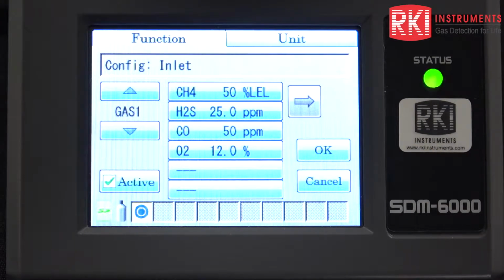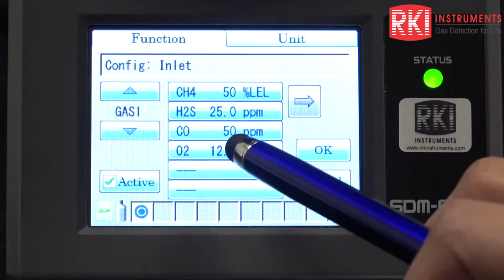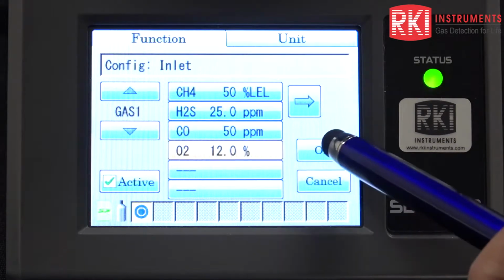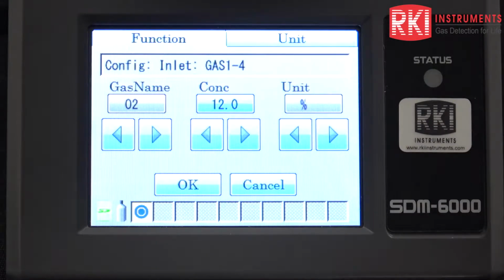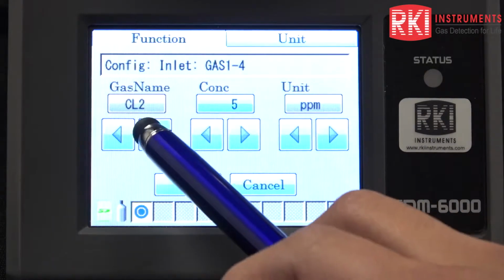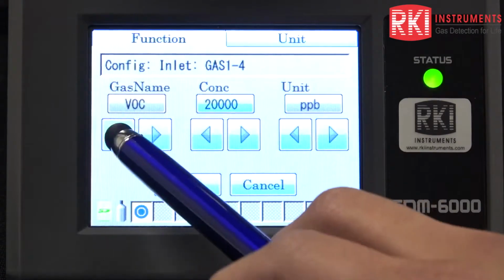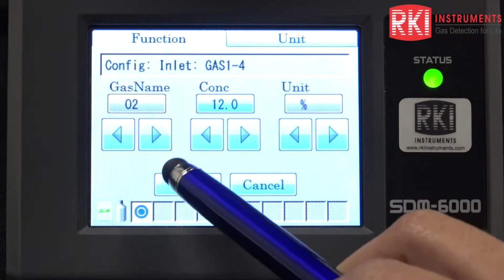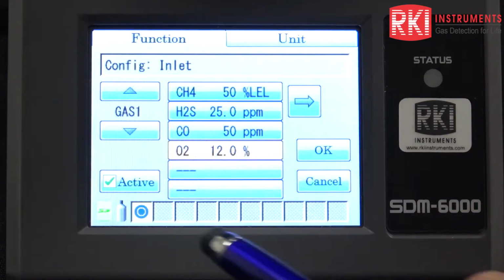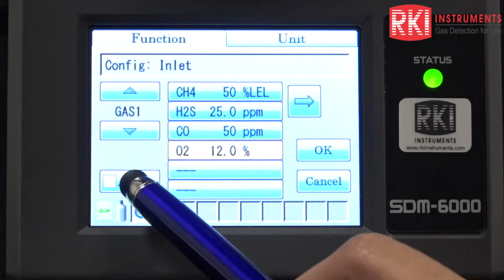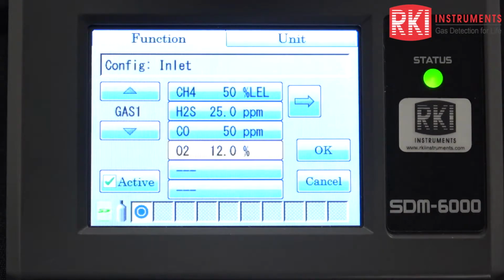So right now, I have gas 1 at CH4 50%, H2S 25, CO 50, and O2 12%. If you need to change it, you just click on one, click the little arrow right there, and you can change it to whatever your gas cylinder is. Right now, I have this concentration, so that is okay. Make sure you have the active box checked. That way it's going to run the gas through. If you have it unchecked, it's going to skip that gas port.